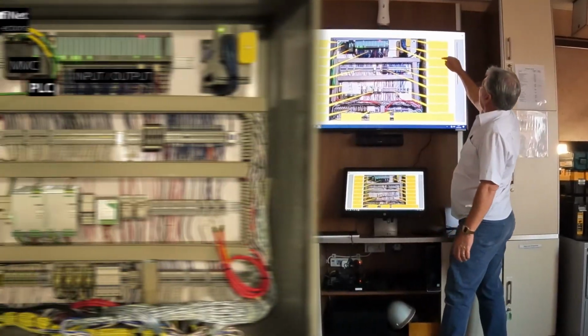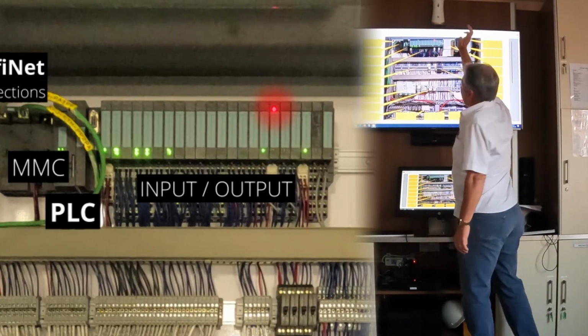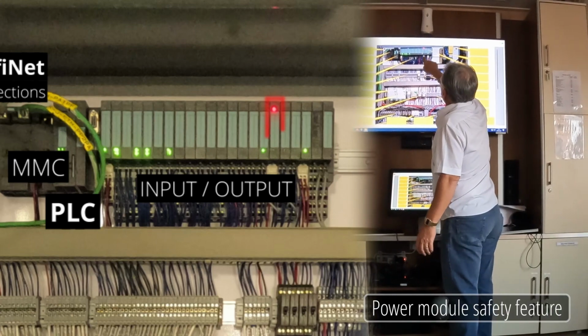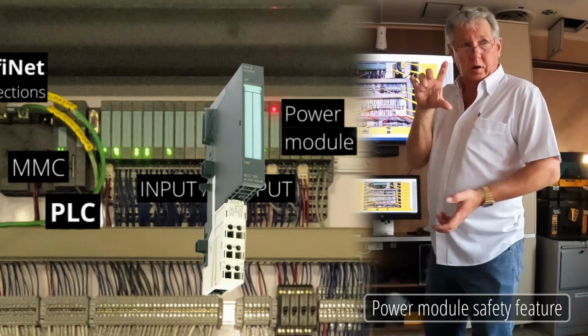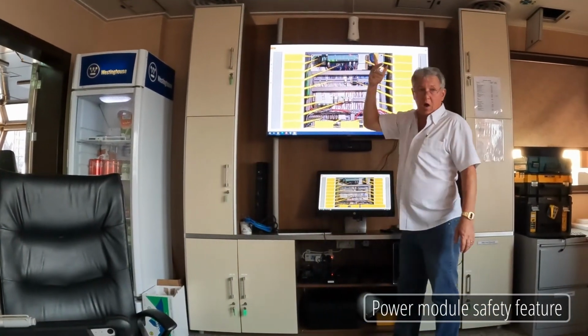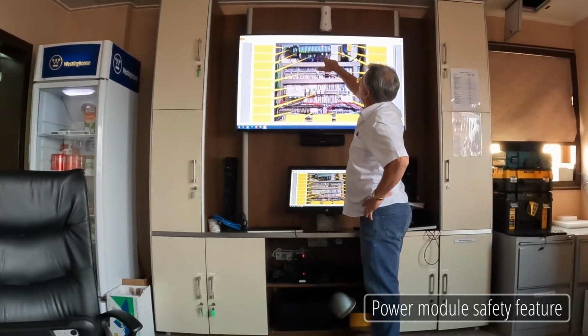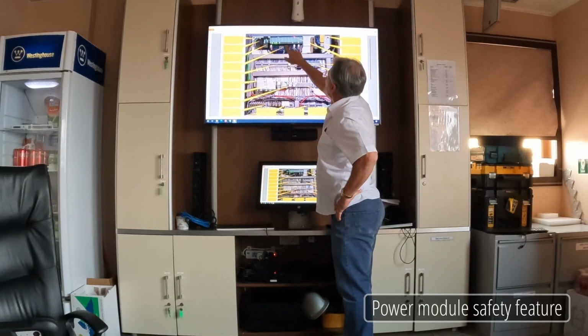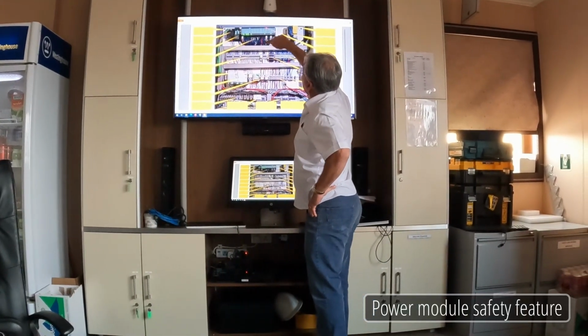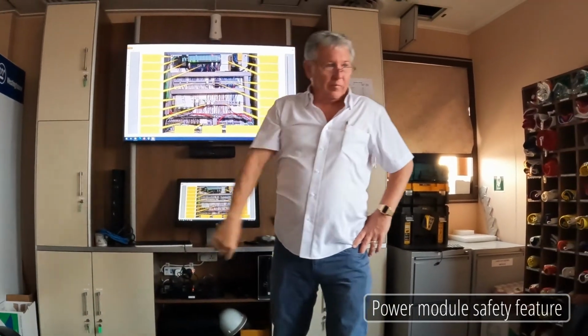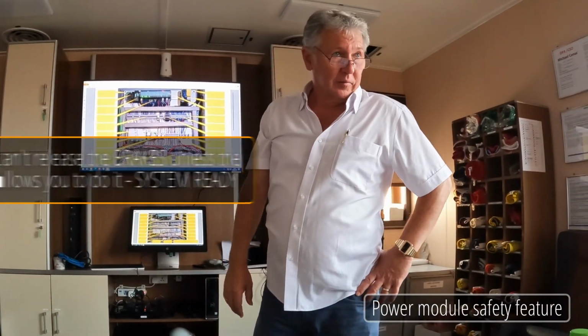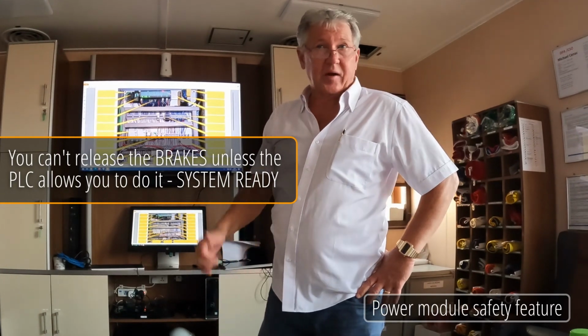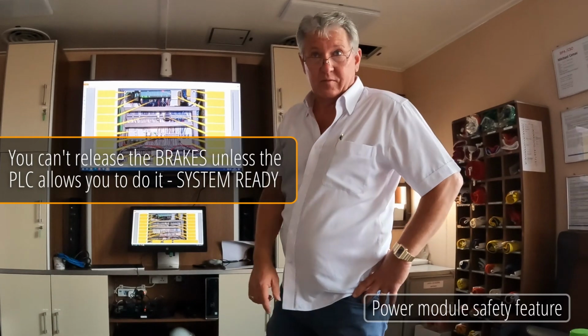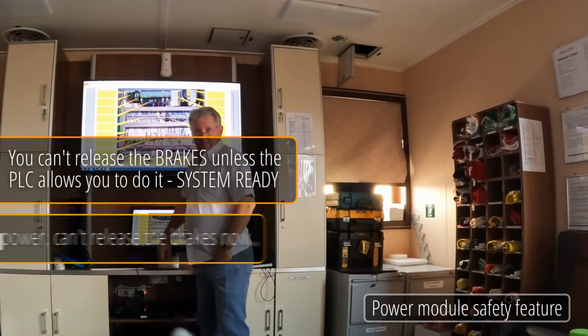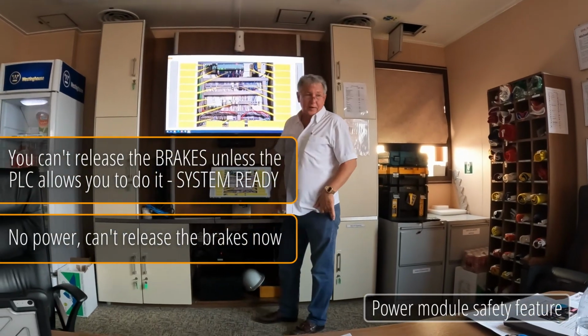Now we're going to jump to this side and go to the third box, this red light. This white guy is not an I/O card, he's actually a power card, a little power card, and he has the ability to turn on and off. What we did was tell the PLC to physically take one of the outputs right into this power guy, and we turn him off. Guess what he runs? The brakes. You ain't doing nothing with the brakes unless you've got system ready and a bunch of other permissions. So this red light means he's off, and this is a secondary safety for the brakes.